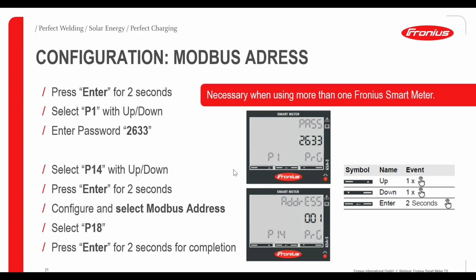Now, after the installation and commissioning, there is still some configuration to be done depending on the number of smart meters you are using in a PV system. If you have just one smart meter in the system, you don't need to do any configuration at all. But as soon as you have more than one smart meter, you need to do this configuration via the display of the smart meter, because when we deliver the smart meters as standard, all of them have the Modbus address 001. As soon as you have a secondary smart meter, you need to change this Modbus address.